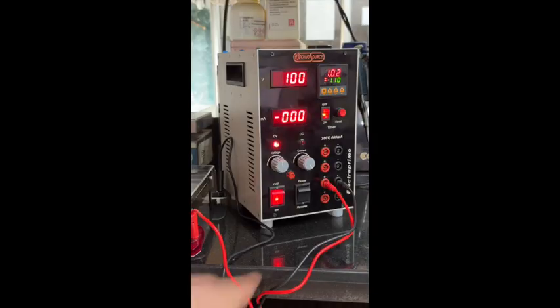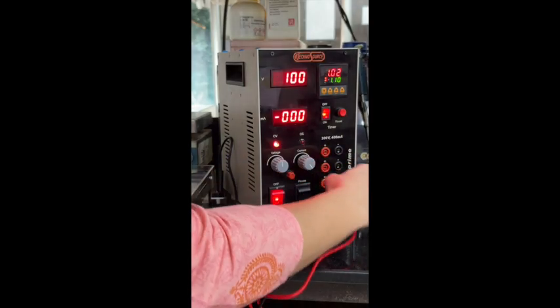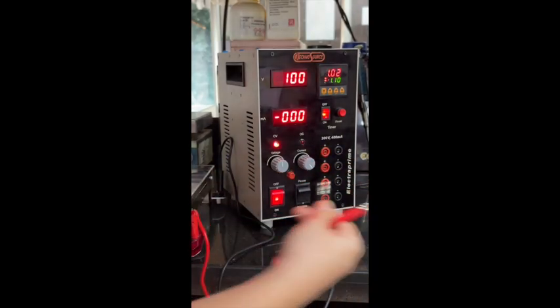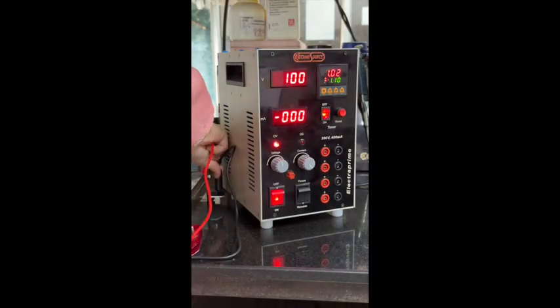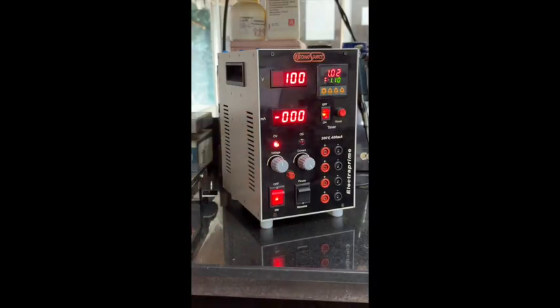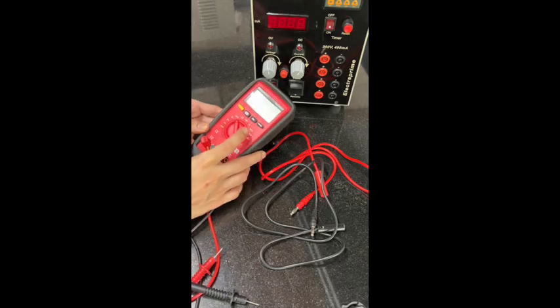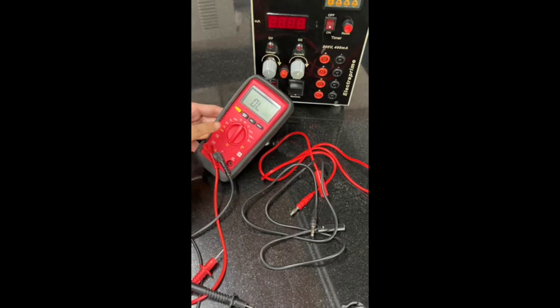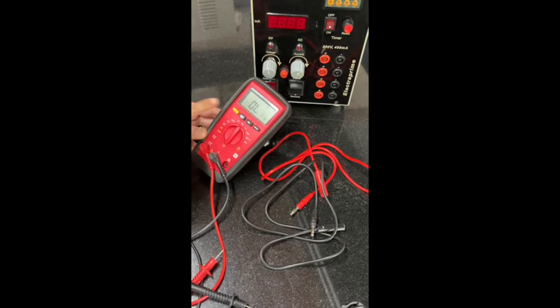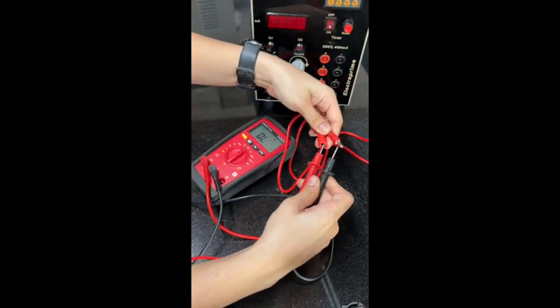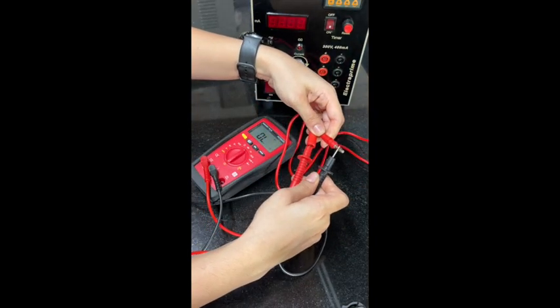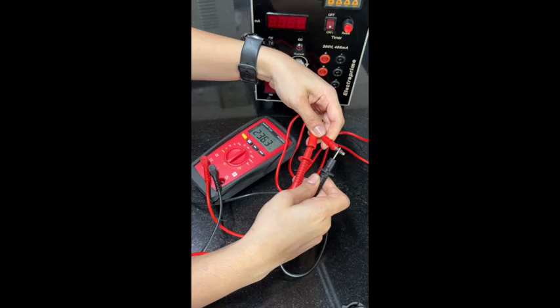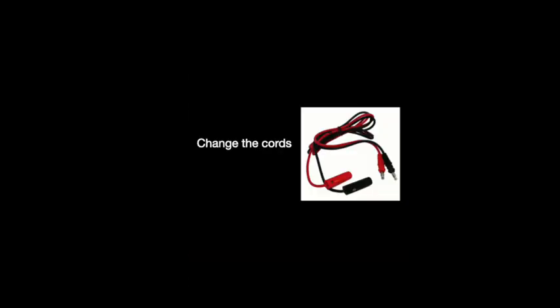Cause number 4. The connecting cords are damaged. Remove the electrical connecting cords from the power supply and the instrument. Using a multimeter set to check connectivity, insert the probes on both ends of the same cord. It should show full connectivity. If the cords are damaged, use new cords.